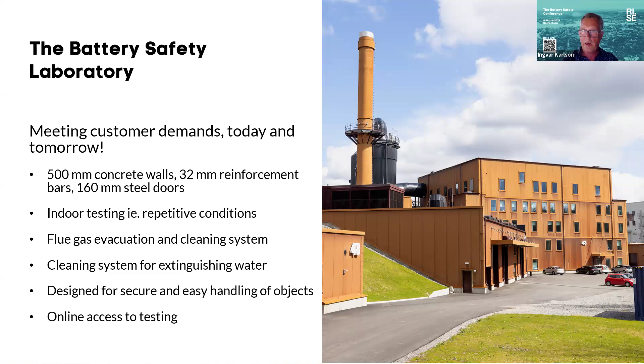Here we have a smoke gas cleaning system, and we have a cleaning system for extinguishing water, and this makes it possible to test a green technology in a green way. We call it the Battery Safety Laboratory, and this is a safe laboratory for battery safety testing, you can say. So we have 500 millimeter concrete walls in the test labs. We have lids in the ceilings of the labs, so if we have a pressure relief, like an explosion and things like that, we can take care of those incidents also. So here we can perform safety tests in a safe and green way.